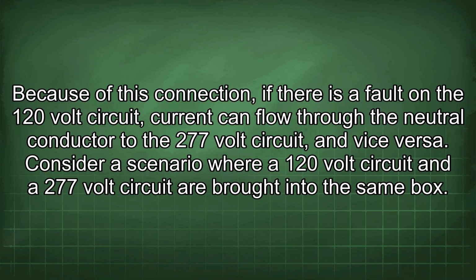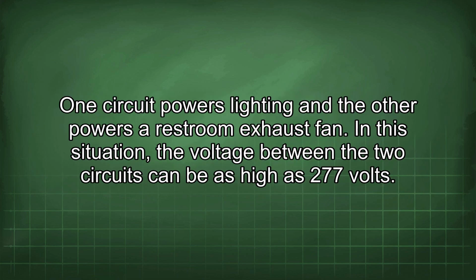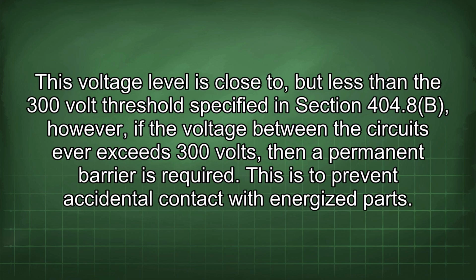Consider a scenario where a 120-volt circuit and a 277-volt circuit are brought into the same box. One circuit powers lighting and the other powers a restroom exhaust fan. In this situation, the voltage between the two circuits can be as high as 277 volts. This voltage level is close to, but less than, the 300-volt threshold specified in section 404.8(B). However, if the voltage between the circuits ever exceeds 300 volts, then a permanent barrier is required.